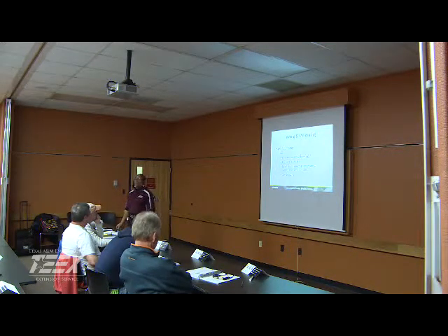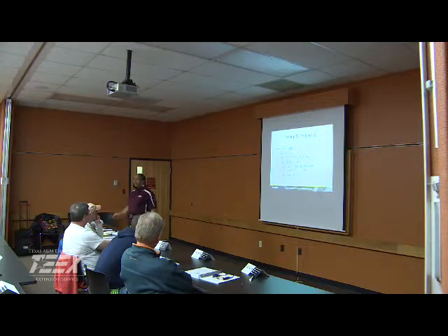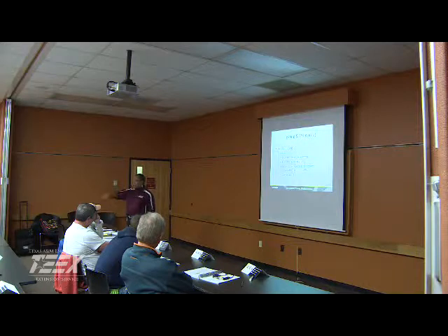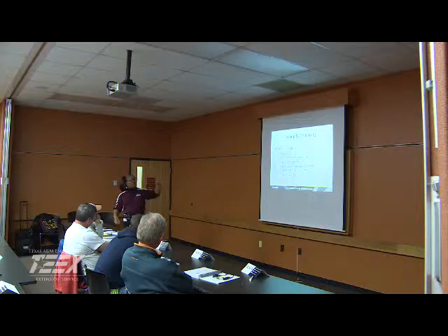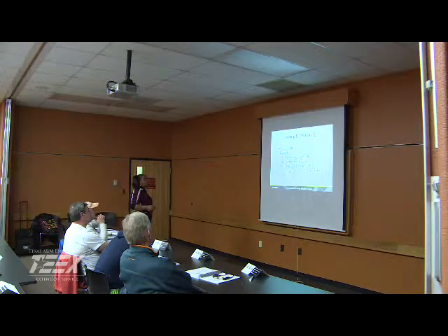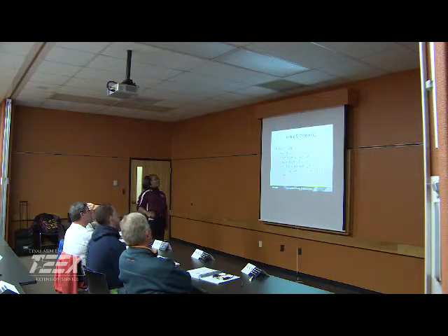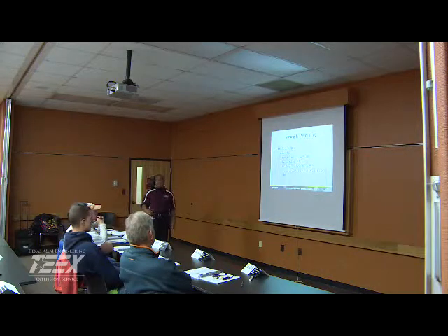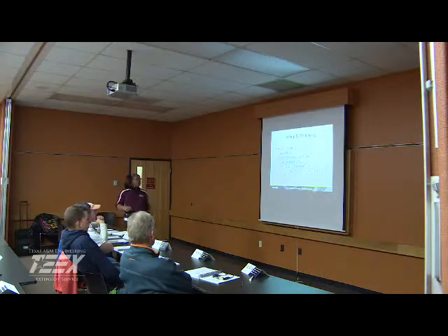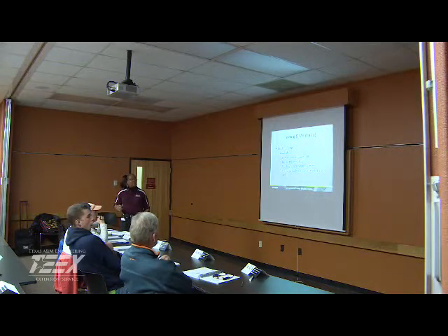What if my pumps are coming on every 15 minutes? Is that good? Depends on how long they're pumping after they come on. They only pump for a minute. Yeah, not too good, right? So we're going to look at cycling less, as far as those pumps coming on and off, to help us with the reduction of pumping sand. So good, you all knew that. You can lower the gallons per minute pump rate, you can cycle the pump less, install sand separation devices if necessary, or correct the problems that you have.